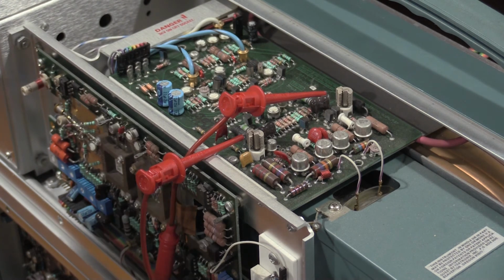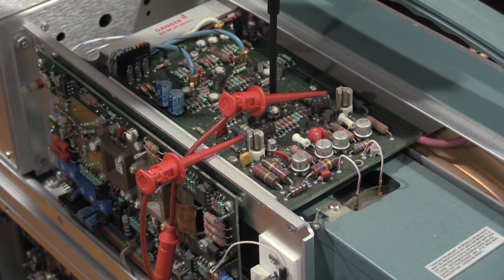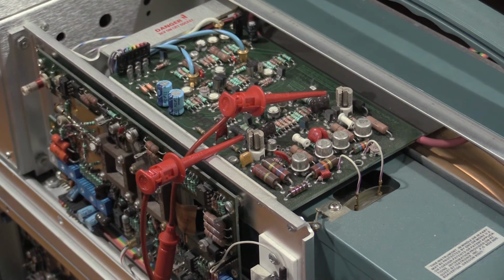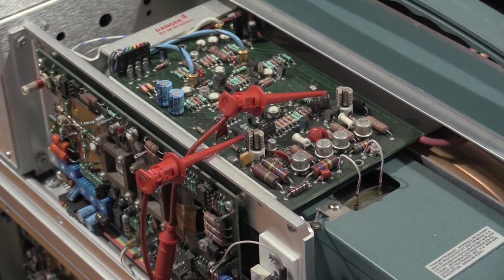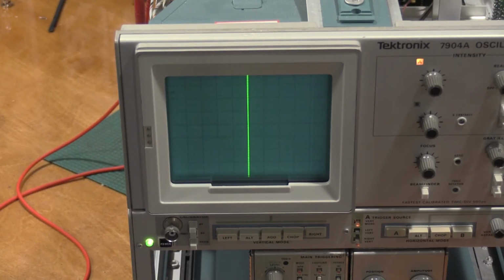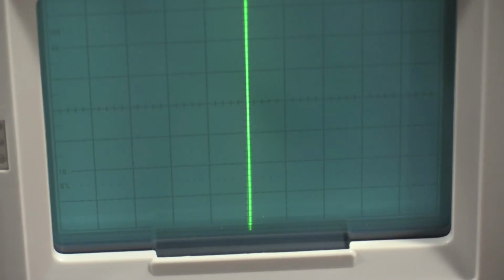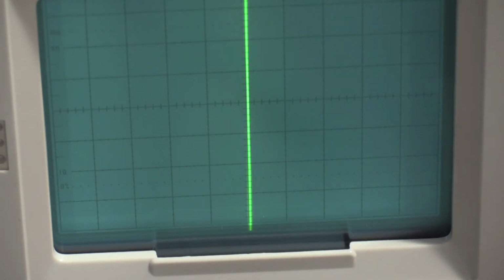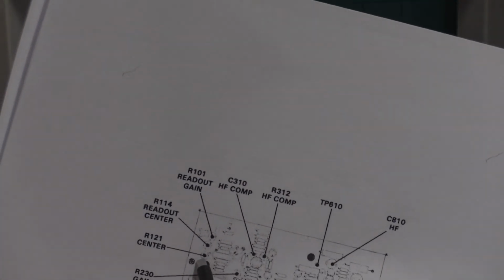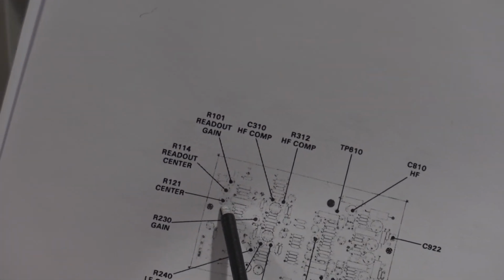R630, the limit center, is actually right here, and it just needs to be lined up on the vertical. And there it is. Okay, my adjustment for the horizontal amplifier centering is slightly off, but not bad. So I'm going to adjust that real quick. That is R121. R121 is right here on the horizontal board.